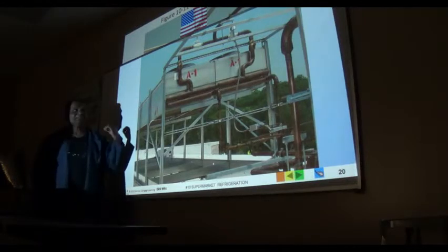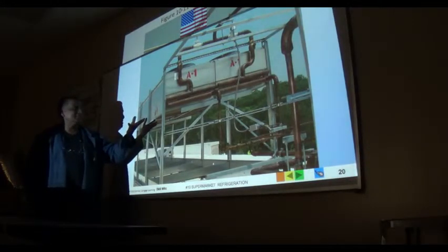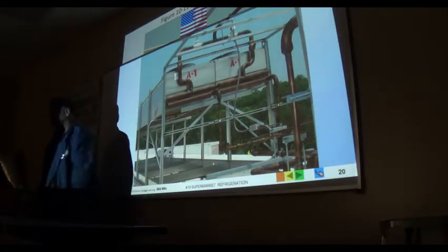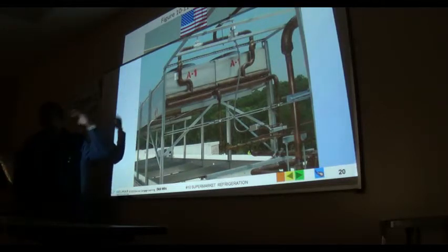Now, on the smaller systems that just have the fan and the coil, a lot of guys go up there when you have high head pressure, and they look down because they're standing up. The coil looks clean, right under the fan. But no, you have to look up because it sucks air in. More often than not, that whole thing is blocked up with soot, dust, bugs, and actually bird feathers, pigeon feathers and pigeon crap. All of that is inside these units at times on the rooftop.